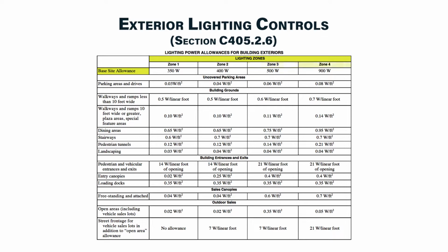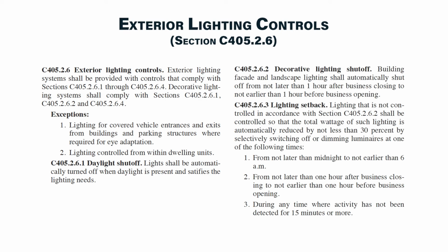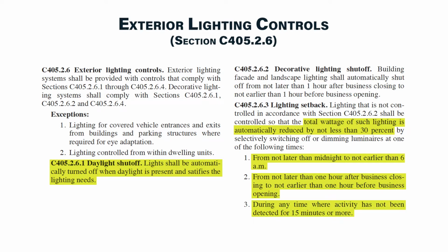IECC and ASHRAE are consistent in this approach. Exterior controls must automatically reduce installed exterior lighting power by 30% or more between the hours of midnight and 6 a.m., or generally during non-operational building hours.